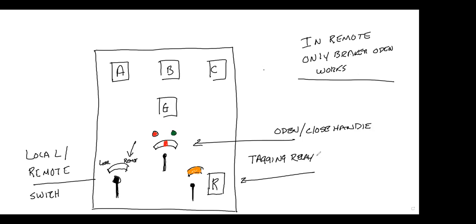Okay. Now, the tagging relay, there's a specific purpose for it down here. If I want to get a hotline work permit and I don't have SCADA, the tagging relay turns off the reclosure. So what are the steps here? I need to go from remote to local. Of course, you're getting permission to do this. You're talking to a guy by radio, and then I'm turning off reclosing. You now have a hotline work permit, right?